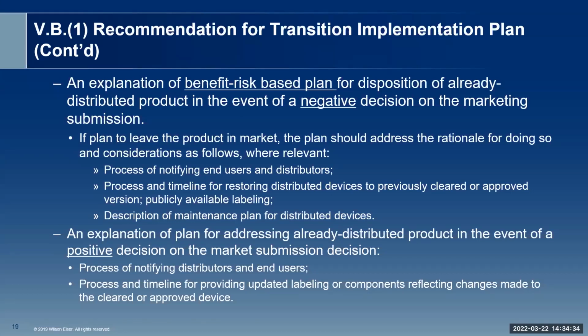And you also need to include an explanation of your plan in case you receive a positive decision on your marketing submission from the FDA, which would include a process of notifying your distributors and end users. And I'm sure you will be very happy to send out that notification letter, starting with, we are very pleased to advise you that our product has now received the FDA's clearance or approval. And also a process and timeline to provide updated labeling or components reflecting the changes made to the cleared or approved devices, if you have not already started on that process yet.